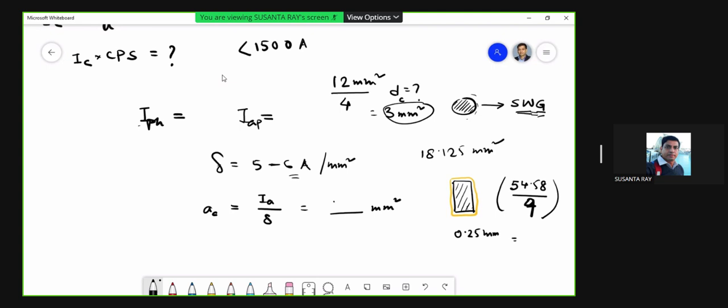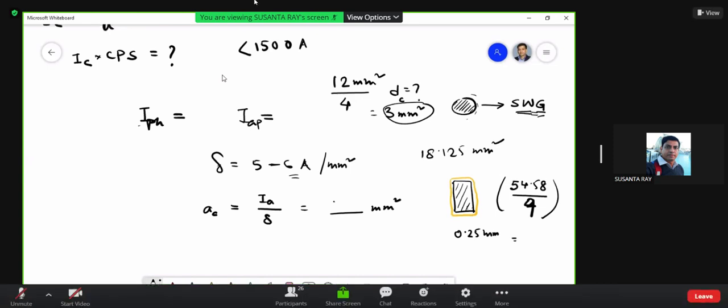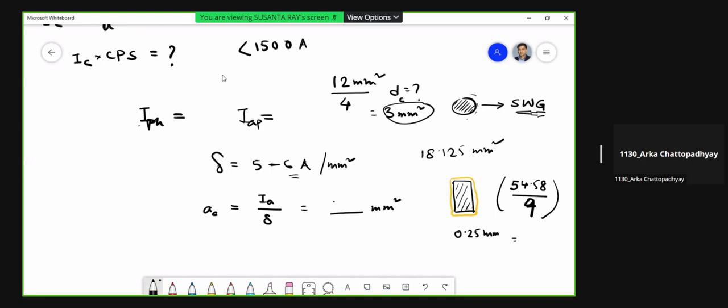I hope it will work out. It says 200 something and it will get more slot area. I think you can accommodate 18 conductors, each having how much did you say, 7 or 8? Sir, 7.39, sir. Okay, 7.3 mm square. You just try.